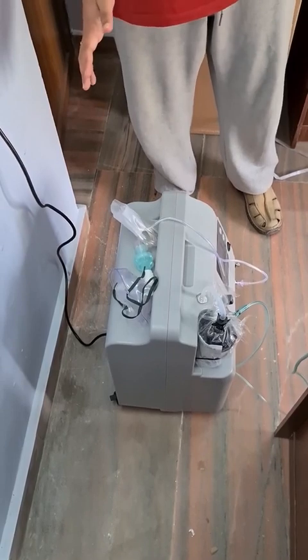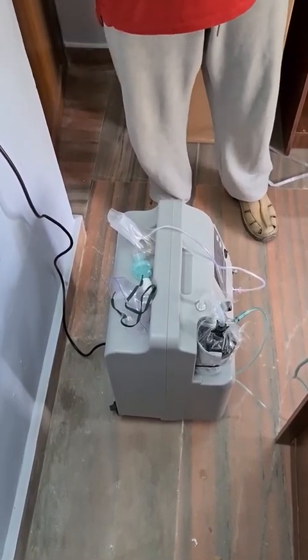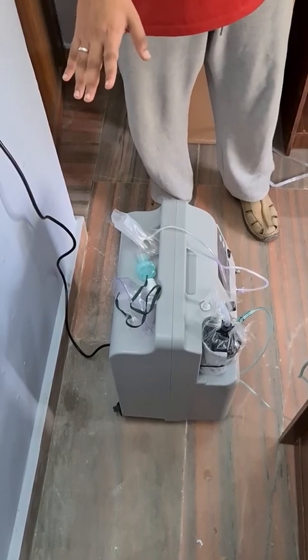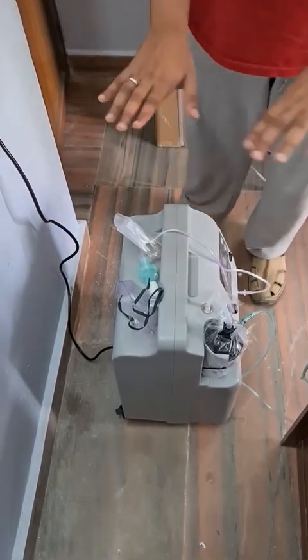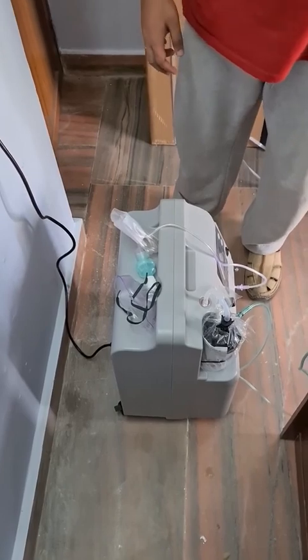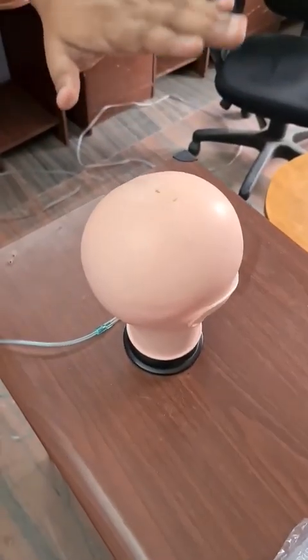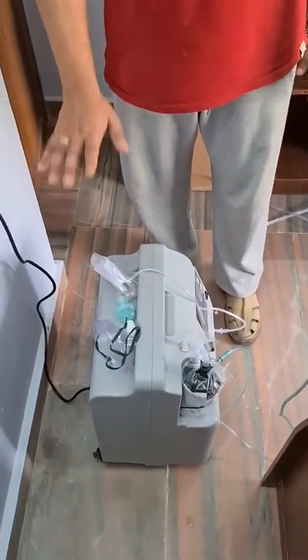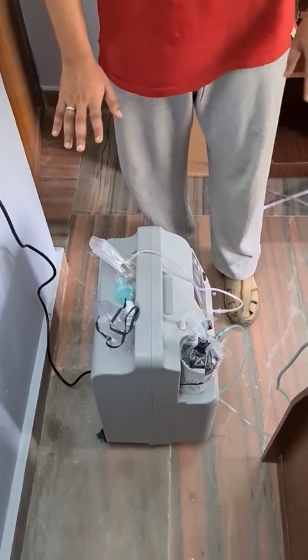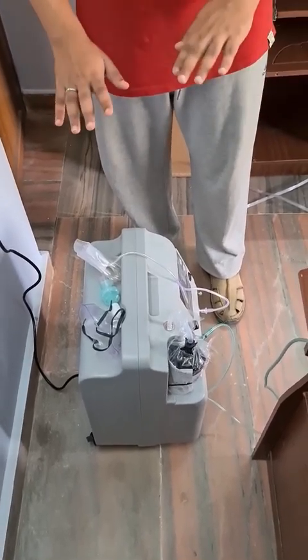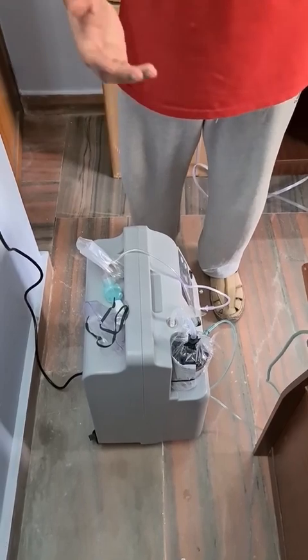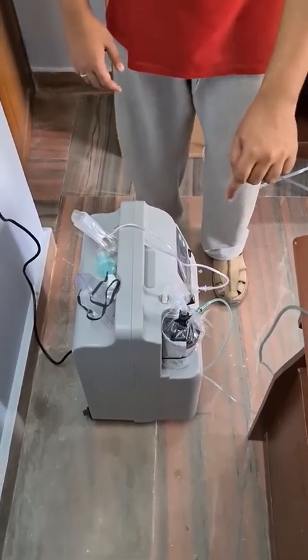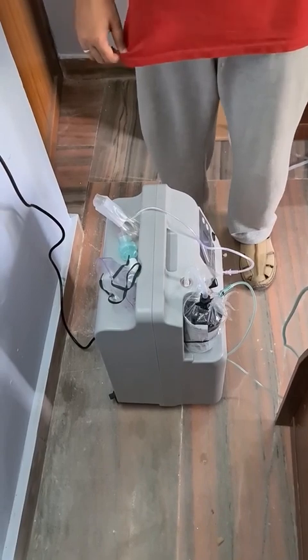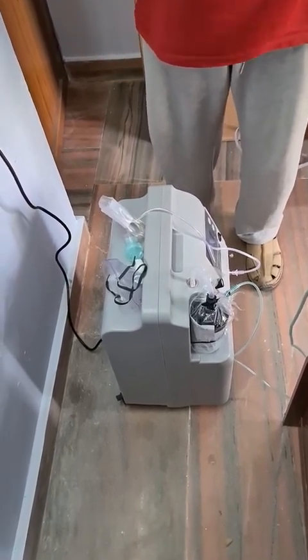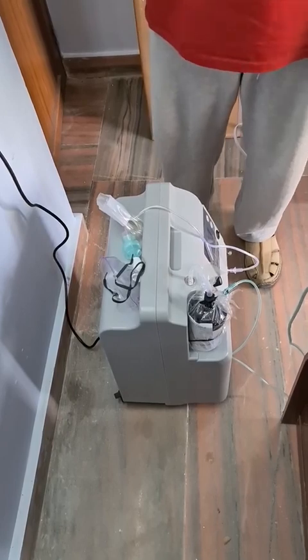For video purposes, we kept this concentrator on the table and showed you. But the correct and only proper procedure is to keep the concentrator at ground level. As you can see, even if the patient is at a higher level, for example on a bed, the concentrator has to be kept only on the ground. It should not be kept on a table and used, because if the table is at an equivalent or higher level compared to the patient, water from the humidifier may pass directly to the patient, and there will be chances of moisture getting trapped in the nasal cannula due to gravity.